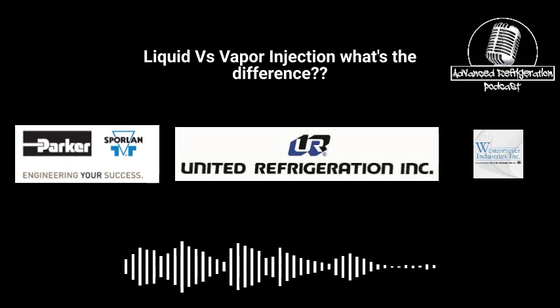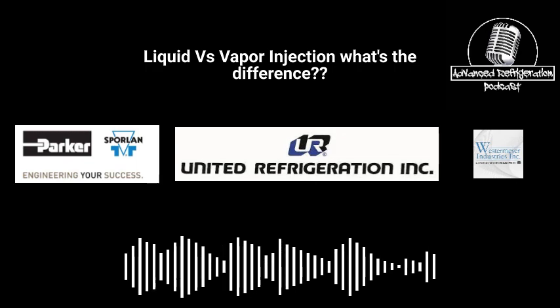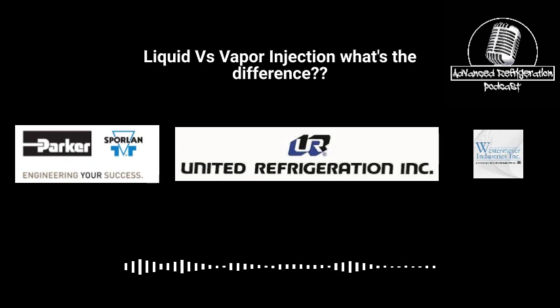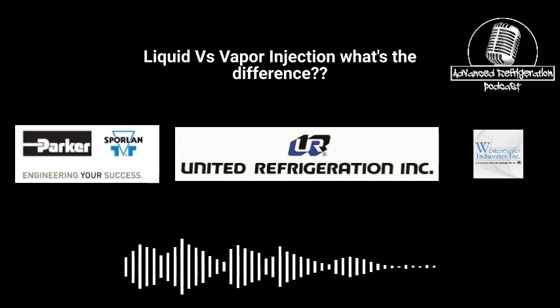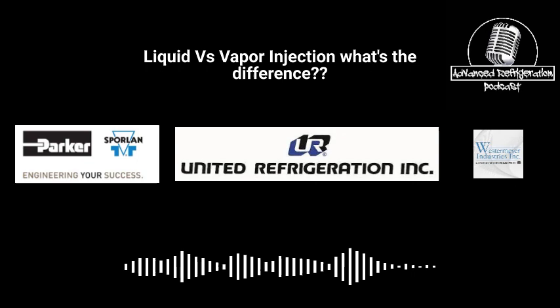In rotary screws, they refer to that as an economizer line. And basically the thought is that there's like a dead spot in there where there's no real compression going on. So injecting that vapor in there helps with that efficiency as well as the cooling effect on that compressor as well.